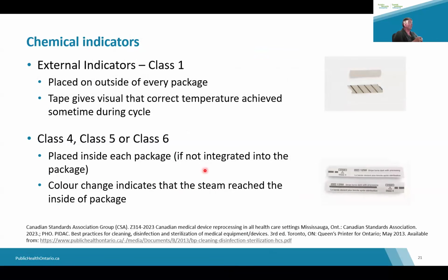And then we have chemical indicators. These can be external indicators or internal indicators. The external indicator is the class 1. That's this stripy one here. You see it on the outside. Make sure you put it on the outside of all of your packages. And this tape just gives you a visual idea that the package has gone through a sterilization cycle at some time. And then inside, you're going to put either a class 4, 5, or 6. It's preferred that you put in a class 5 because it is better. It means it's testing against all the critical values.